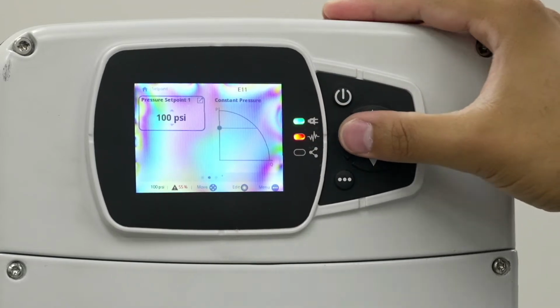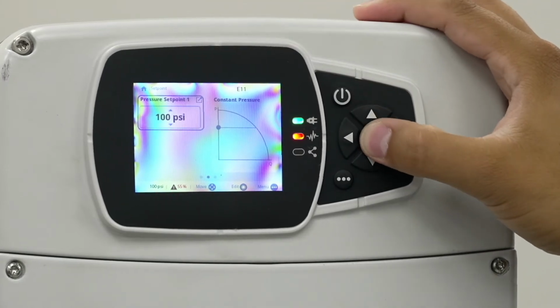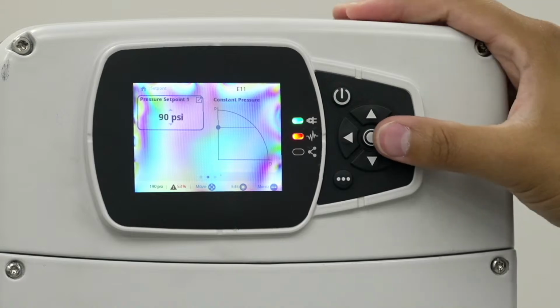As I touched on, there's kind of widgets you can mess with on the various screens. If I scrolled over to the next one, this is your pressure set point. If you wanted to adjust this, I would click enter on it. I can reduce the set point to 90 PSI if I needed to, right on the fly from the home screens. The next one is auto start.